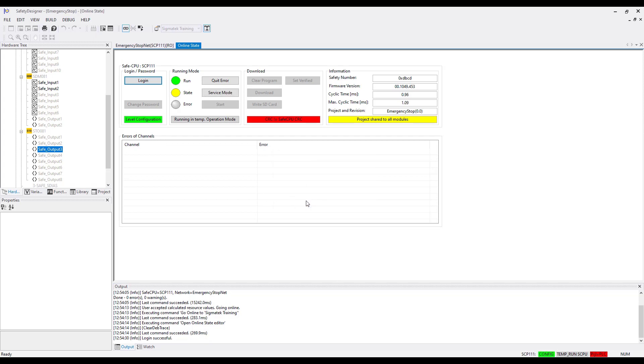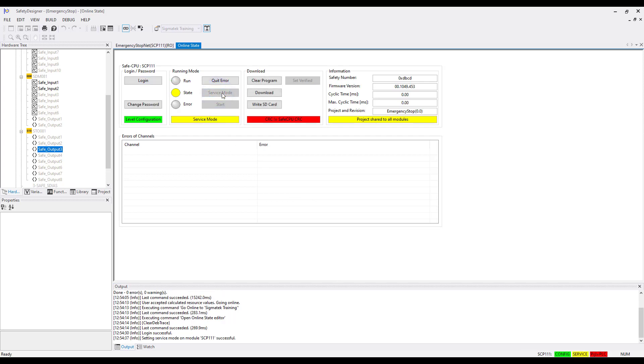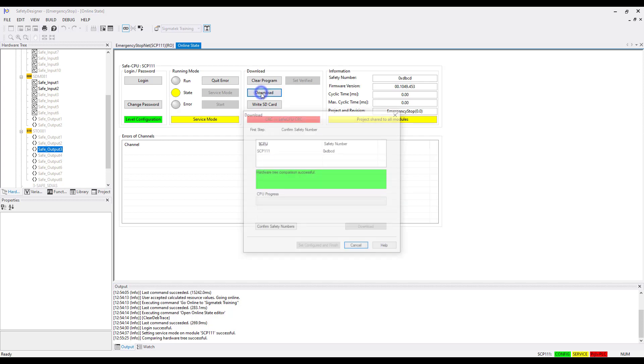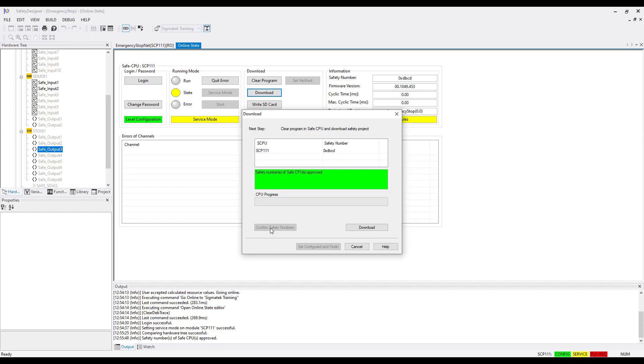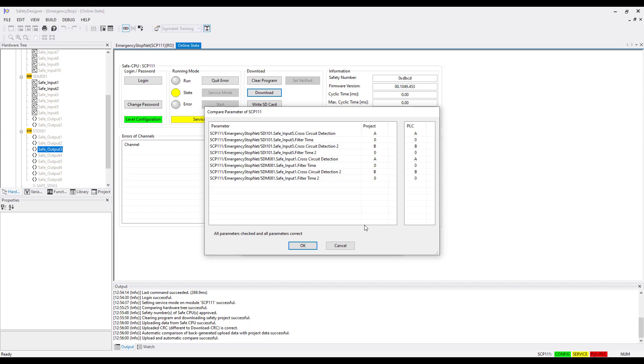Once logged in, you have to switch to service mode. If you have never downloaded a project to the controller, the download button is active without service mode — click the Download button. For downloading, you have to confirm the safety number. The safety number is printed on your safe CPU. Compare this number to the number shown in the SafetyDesigner. If the numbers match, click Confirm Safety Number. The download button becomes active and you can download the project. Once loaded, a window appears where you can compare the project with the hardware — click OK.